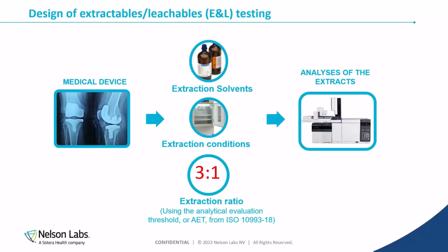So there are things that we consider when we design the study. So again, this is fast track, but we have to consider these elements. First, we always consider the medical device. What are the materials used? How does it contact the patient? How long does it contact the patient? Making sure while we're trying to do these exaggerated extraction conditions, that we design them correctly. So when we take those considerations of the medical device into play, we then design the extraction solvents. Typically, we use 3 solvents: a polar, midpolar, and apolar solvent.